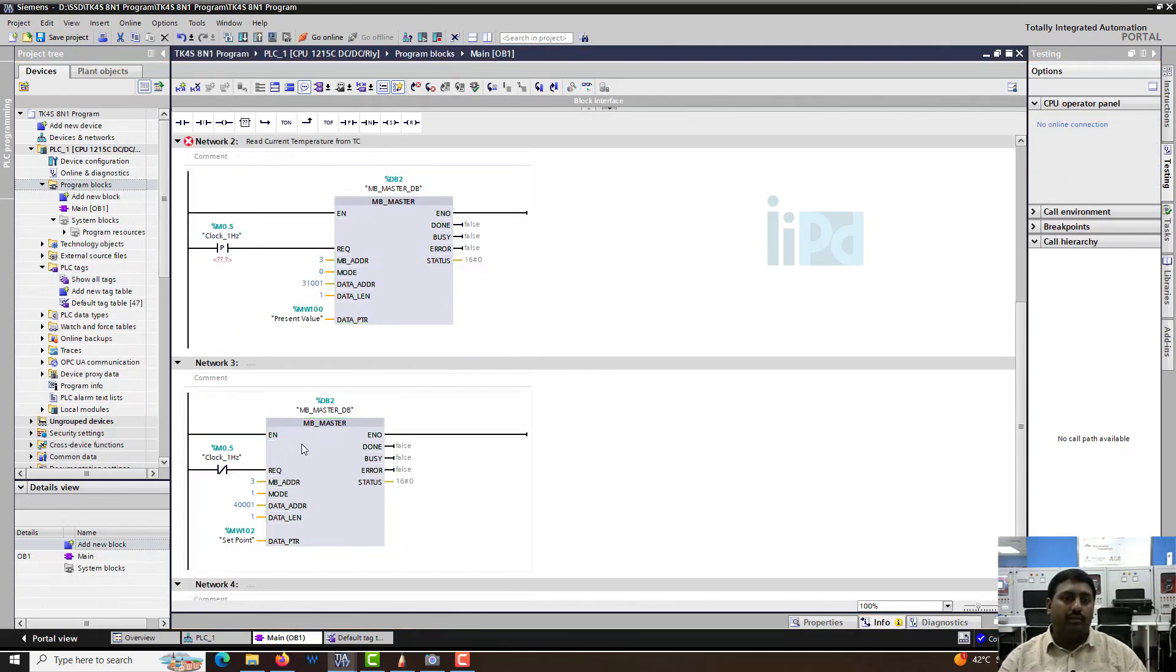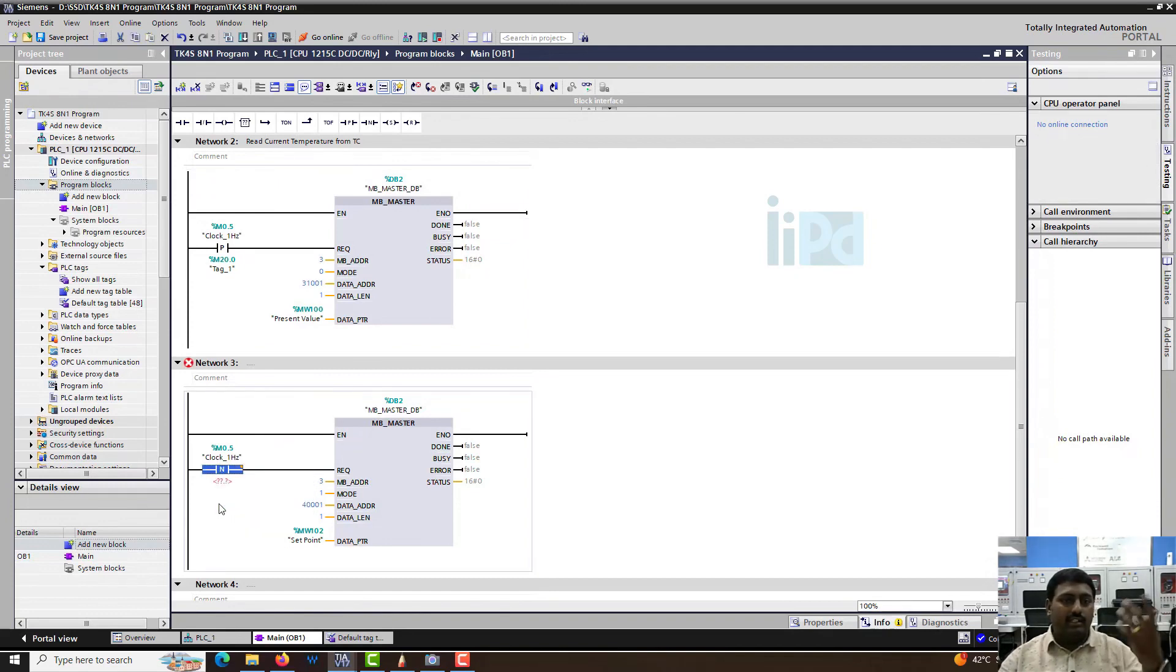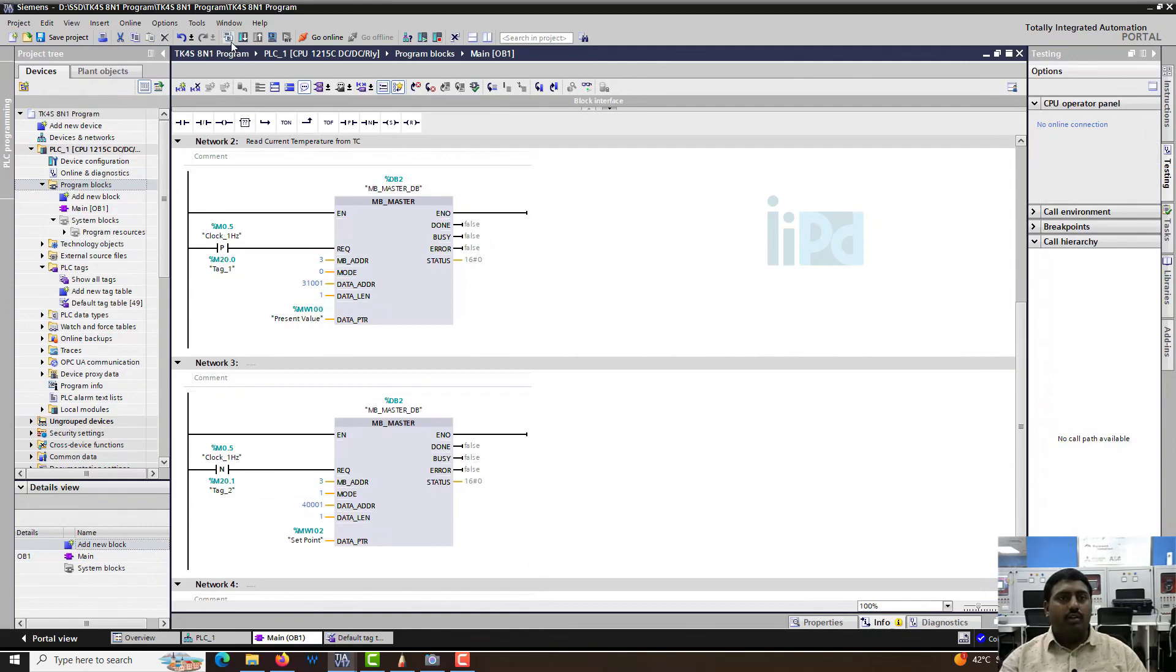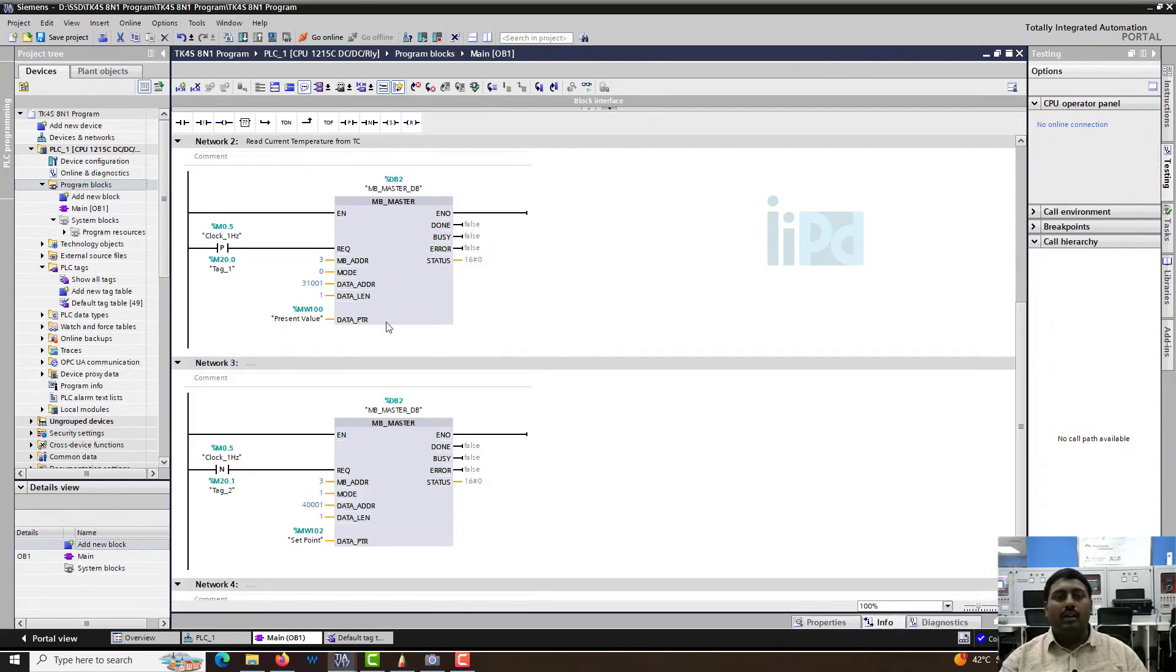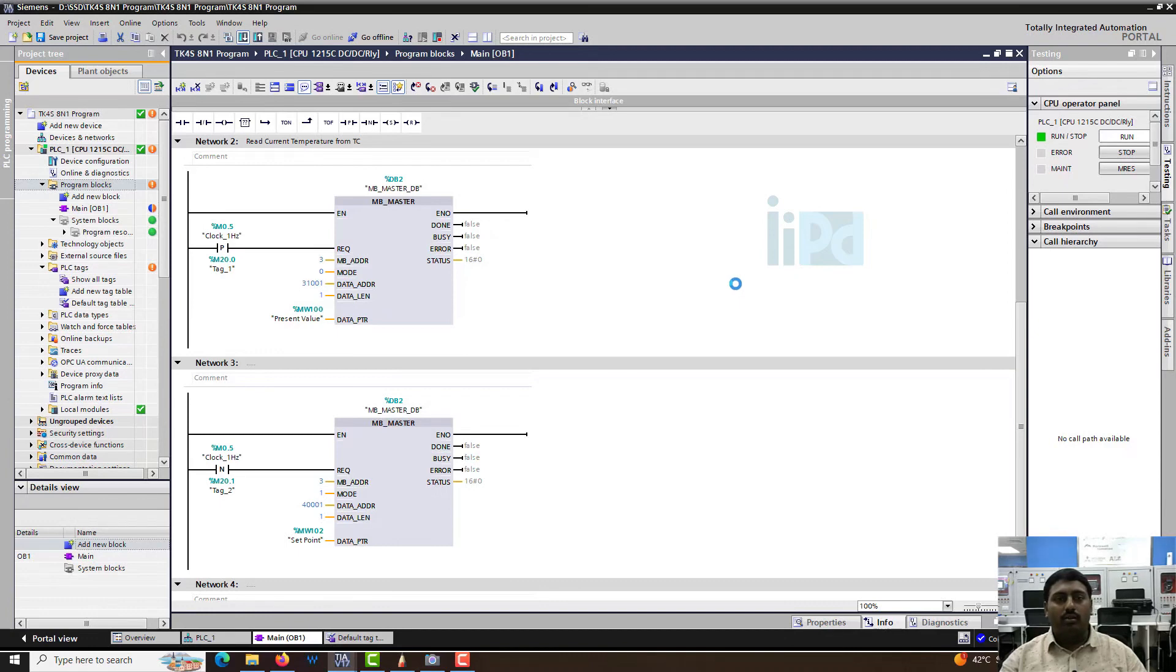Instead of directly giving a bit like this, it's better to give a positive trigger here instead of a complete half a second pulse, because the request has to be instantaneous. It's always better to replace this with a positive trigger and give one dummy memory, m20.0. And here, let's give a negative trigger, m20.1. That means this will execute when it is on and this will execute when it is off. This will be more stable communication, and it will not affect the program because the request is only given in an instant. Let's download this again.